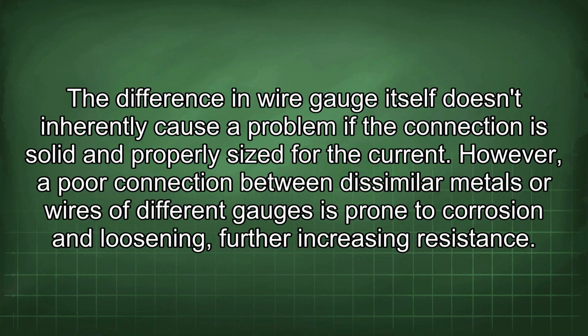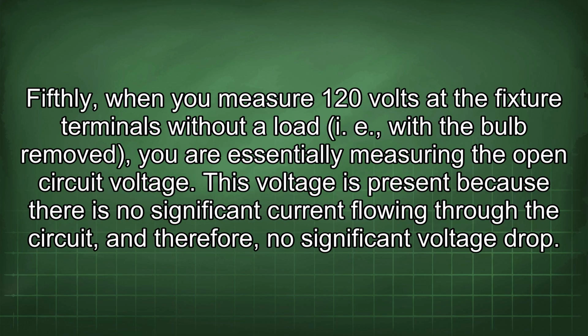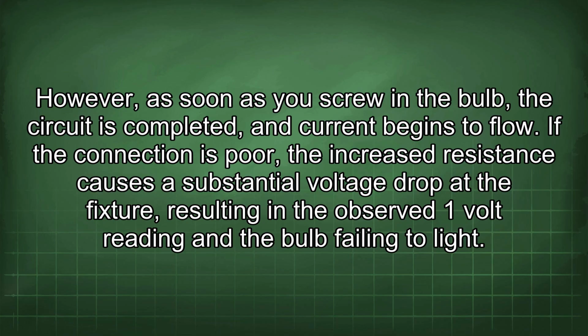The difference in wire gauge itself doesn't inherently cause a problem if the connection is solid and properly sized for the current. However, a poor connection between dissimilar metals or wires of different gauges is prone to corrosion and loosening, further increasing resistance. Fifthly, when you measure 120 volts at the fixture terminals without a load, i.e., with the bulb removed, you are essentially measuring the open circuit voltage. This voltage is present because there is no significant current flowing through the circuit, and therefore, no significant voltage drop. However, as soon as you screw in the bulb, the circuit is completed and current begins to flow. If the connection is poor, the increased resistance causes a substantial voltage drop at the fixture, resulting in the observed 1 volt reading and the bulb failing to light.